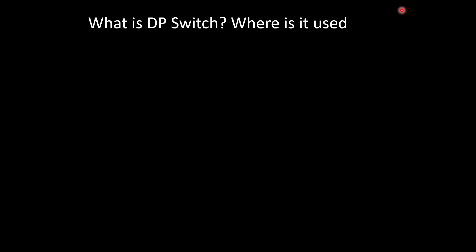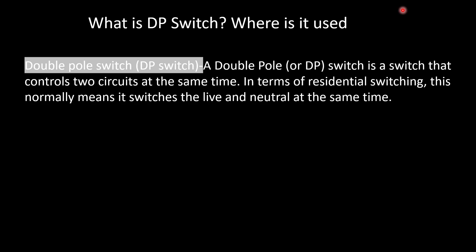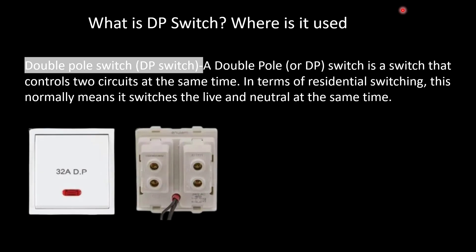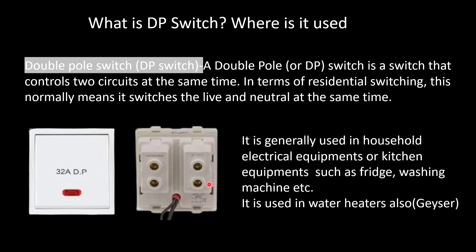What is a DP switch and where is it used? A Double Pole (DP) switch is a switch that controls two circuits at the same time. In terms of residential switching, it switches the live and neutral at the same time. In SP switches, only the phase comes through; in DP switches, both phase and neutral come through. The back side of a DP switch has four terminals, whereas an SP switch has two terminals. It is generally used in household electrical equipment such as fridges, washing machines, and water heaters.